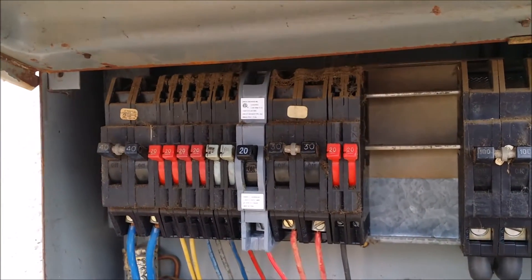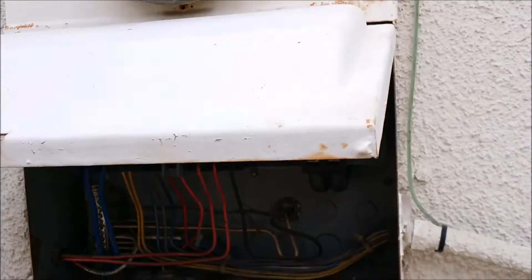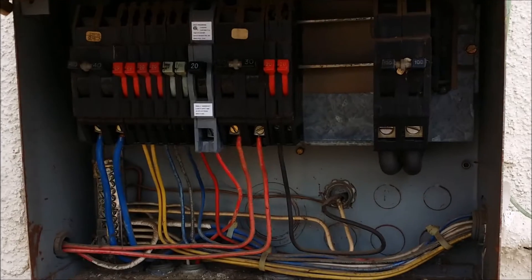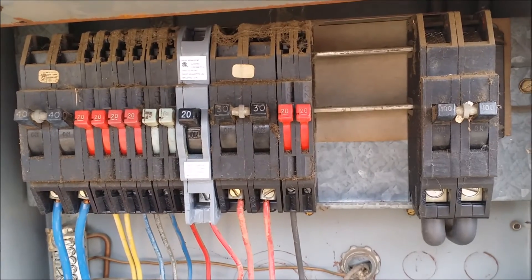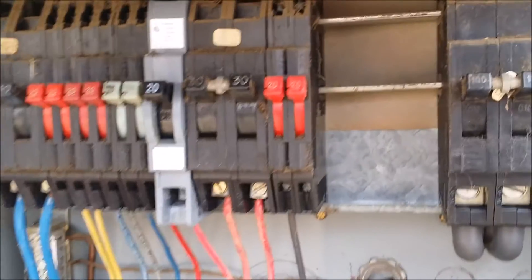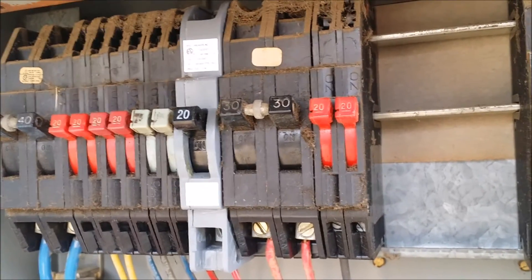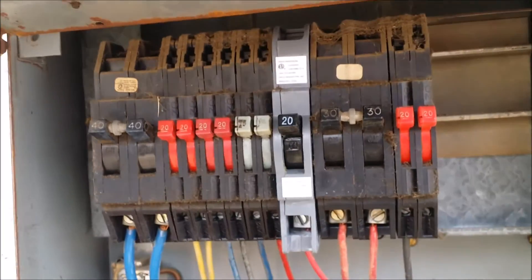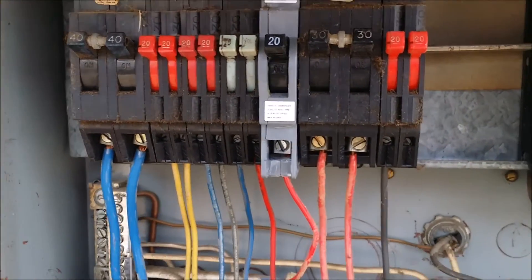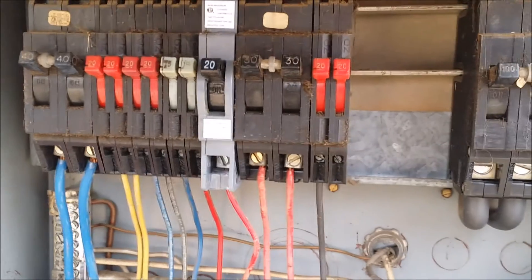This is Greg Noyce with tip number 396. Today I'm doing a house with an older Zinsco type of panel and I see a lot of these in houses from the 60s, 70s, and 80s. They come with two power bars in there made out of aluminum, and the breakers have a metal contact, so they have a dissimilar metal issue. Also, the springs get loose on these breakers over time, and you have a mismatched breaker as well.